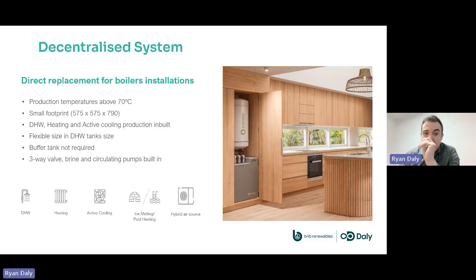If you have a retrofit project, this particular model can achieve 70 degrees flow temperature. It's got a very small footprint, smaller than a normal domestic appliance. This particular heat pump can produce hot water, heating and cooling all in one unit. You can be flexible in terms of your hot water tank. You can size that appropriately for the building. No buffer tank is required as the heat pump is modulating its output. And with our particular solution, all the equipment in terms of the pumps and the three-way valve, the switch between heating and hot water, is all built into the one unit. So you don't have any external pumps or anything like that, which is one of the benefits of it.